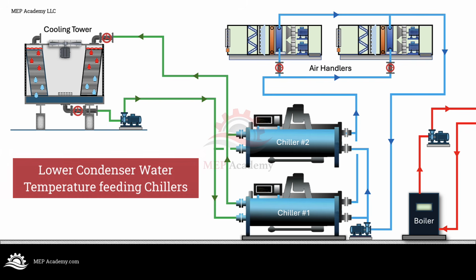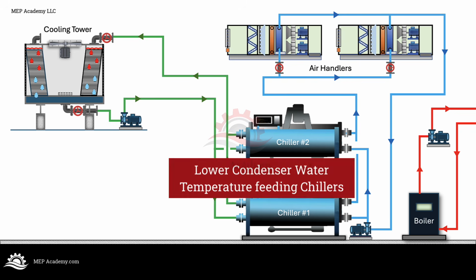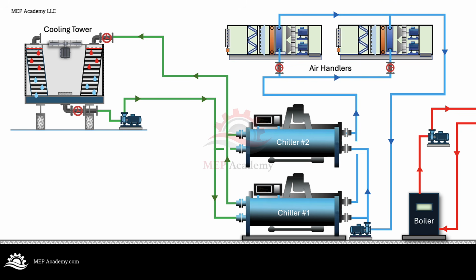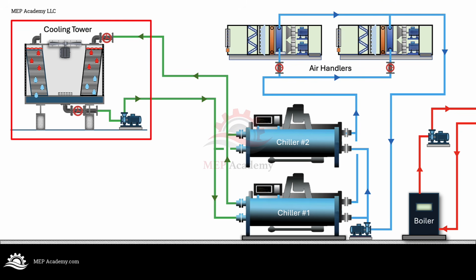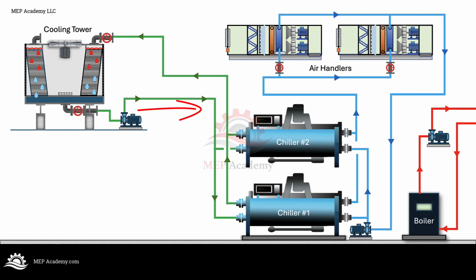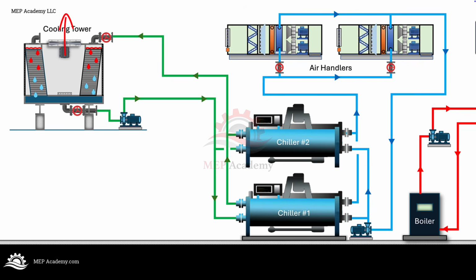Picture a central plant with several large water-cooled chillers. The main chillers are connected to a condenser water loop and cooling towers. Under normal operation, condenser water leaves the cooling tower and flows to the chillers. The chillers reject heat into that condenser water. The warmer condenser water then returns to the cooling tower, where the heat is rejected outdoors. The temperature of the condenser water matters. When the condenser water entering the chiller is cooler, the chiller usually has an easier time rejecting heat.